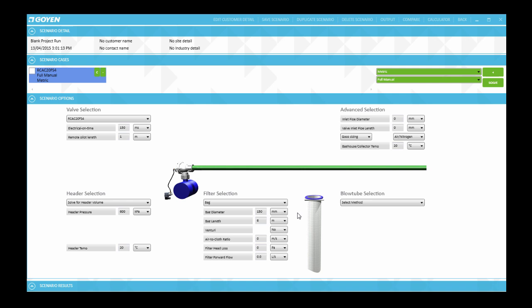Then that is followed by the next parameter which is the provision of using a Venturi. Now the Venturi option should only be used for those cases that have a filter bag diameter of either 5 inches or 6 inches. Let's just say in this case there is a Venturi. So we select yes.